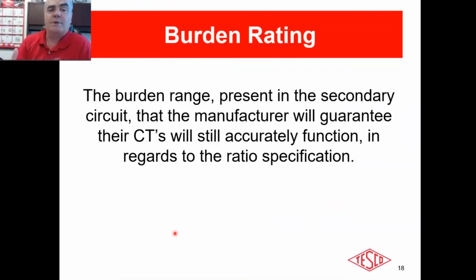Most utilities will say that they give you a range. Once you go beyond that range, you have to go up in the size of wire that you use. You need a thicker wire. Why is that? Because that thicker wire has a lower resistance, a lower burden. So, oh, you got to go 15 feet. Sorry, you got to go up. And that makes that wire a lot more expensive for the utility because there's a lot more of it and it's a much thicker wire. And it's a lot harder to work with. If you ever tried doing that, it's a pain in the butt. So you'd rather not do that. You want to keep them together.